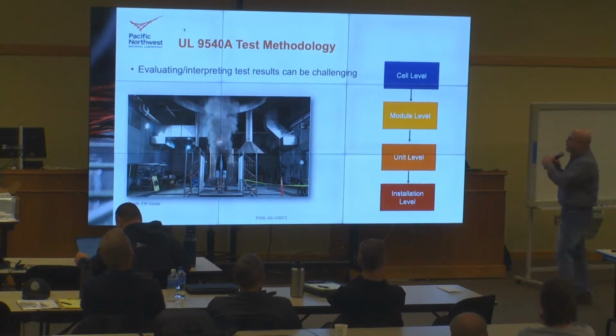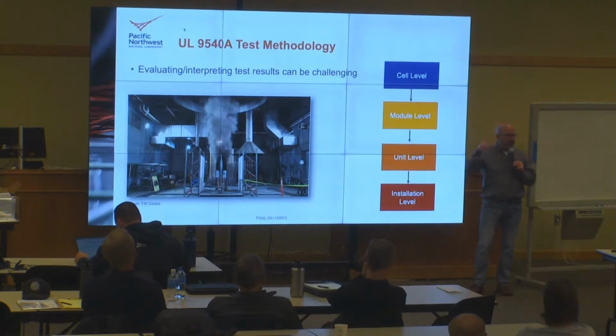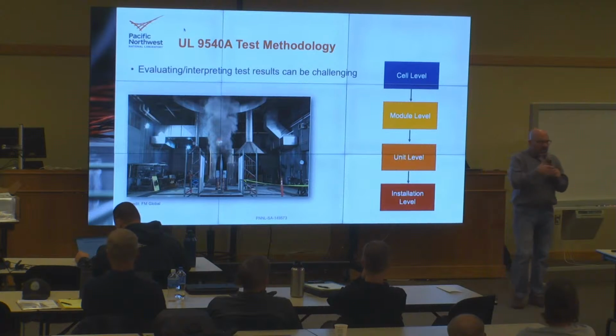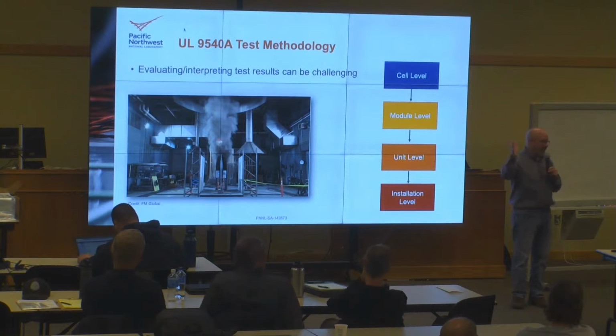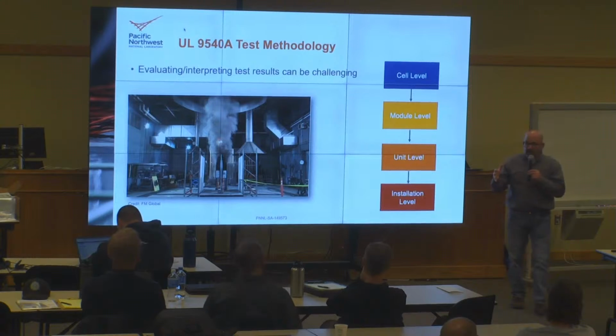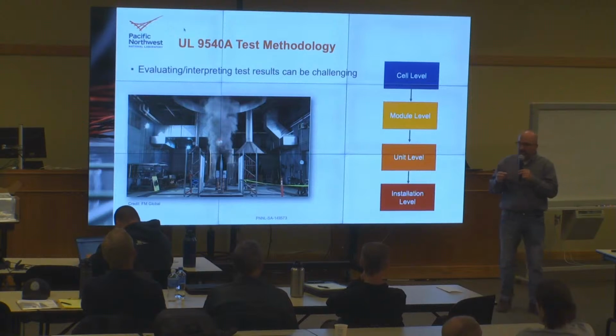So now we've determined it does go into thermal runaway and produces flammable gas. We now do a module level test, where we want to see what it takes to drive propagation. You have to heat cells until you get a fire in an unheated cell. You might need to heat many 18650 cells to drive one unheated cell into propagation and thermal runaway. With a prismatic or pouch cell, you might only need to heat one and it's off to the races. So what we're seeing now are modules designed with unique materials, phase change materials, aerogels, that really limit propagation.